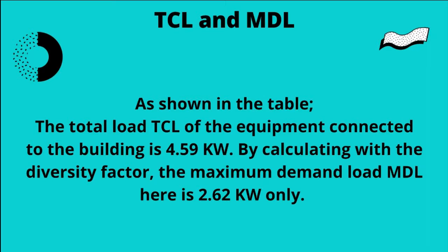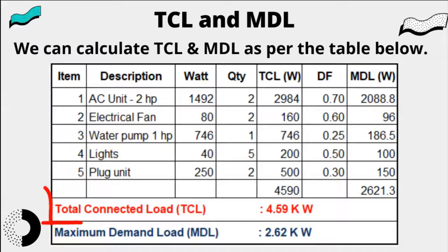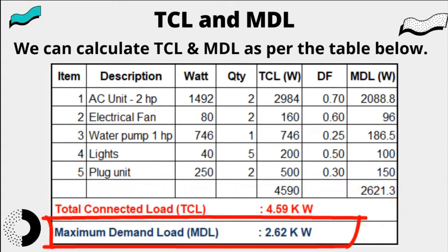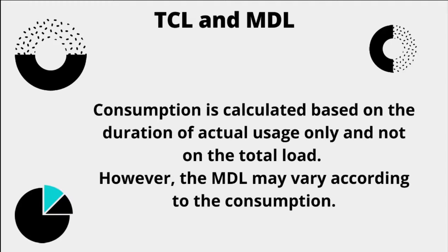As shown in the table, the total connected load of the building is 4.59 kW. According to the diversity factor, the maximum demand load is only 2.62 kW. Consumption is calculated based on the duration of actual usage only, and not on the total load.